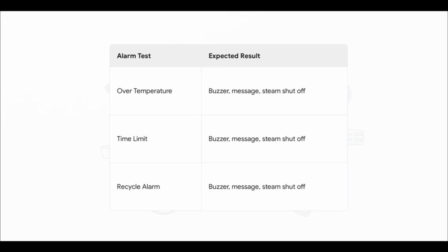A huge part of OQ is deliberately triggering alarms to prove the machine fails safely. So for an over-temperature alarm, we don't just want a little light to blink. We need documented proof that the buzzer goes off, an error message is printed, and, most importantly, the steam supply is instantly cut off. We're proving the safety features work exactly as they should.